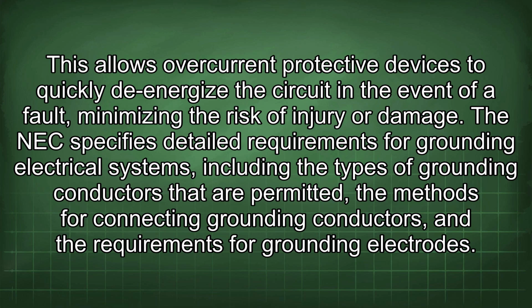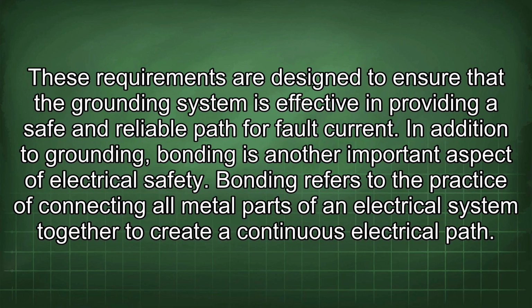The NEC specifies detailed requirements for grounding electrical systems, including the types of grounding conductors that are permitted, the methods for connecting grounding conductors, and the requirements for grounding electrodes. These requirements are designed to ensure that the grounding system is effective in providing a safe and reliable path for fault current. In addition to grounding, bonding is another important aspect of electrical safety.